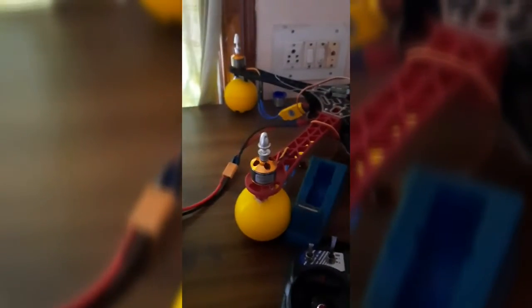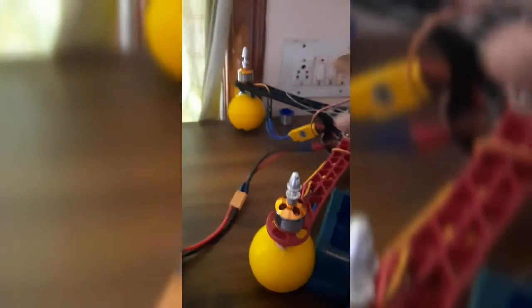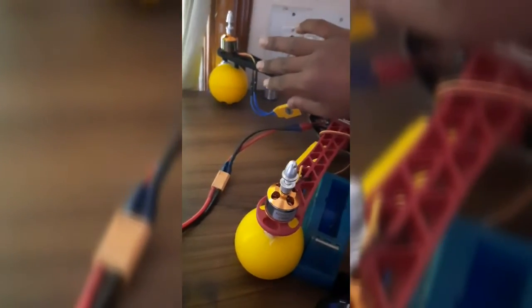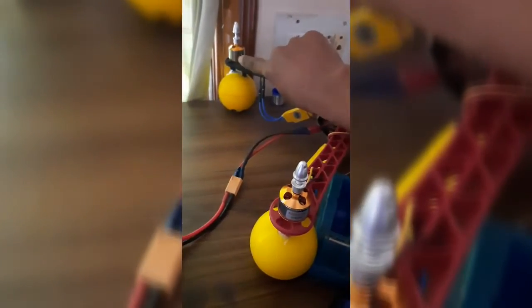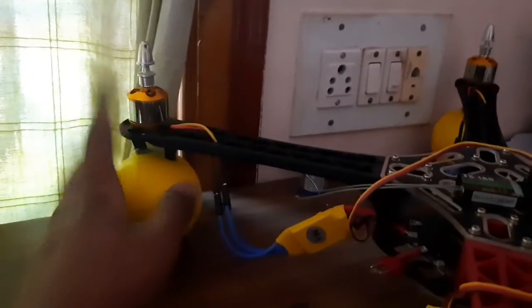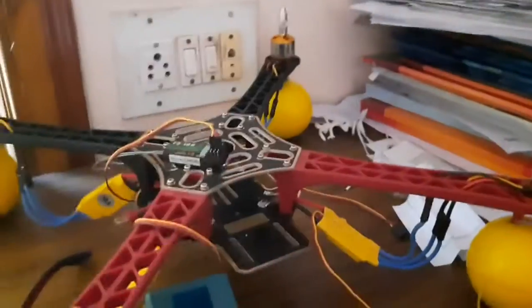The motor is in clockwise direction. If the motor is not in clockwise direction, change any of the two wires and it will be made anti-clockwise. As it is correct, I will not change it. If any two wires have been interchanged, now the motor is turning in the correct direction. Continue this for all 4 motors.